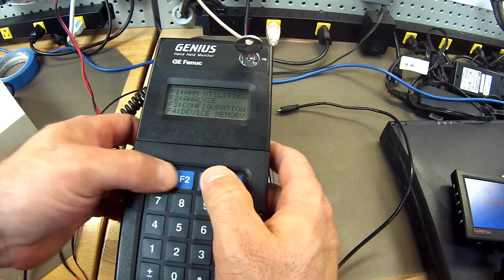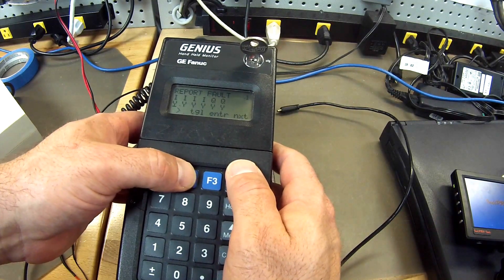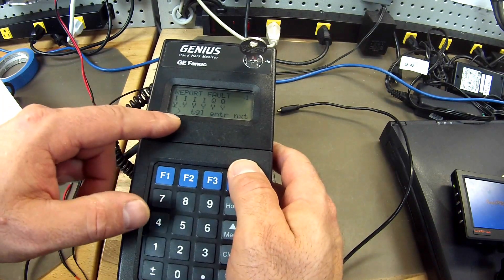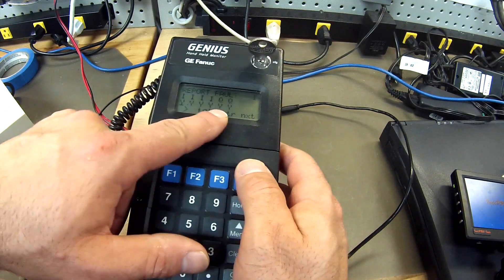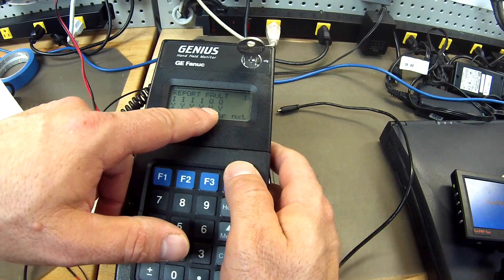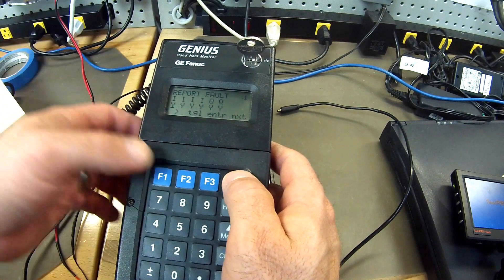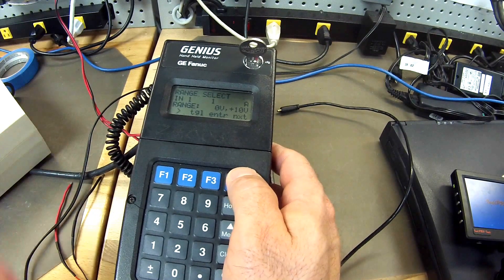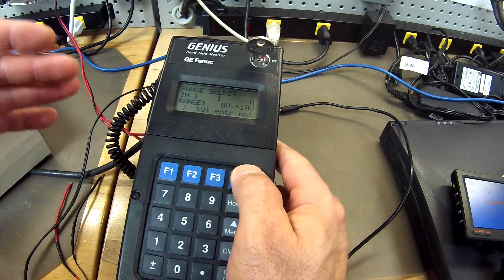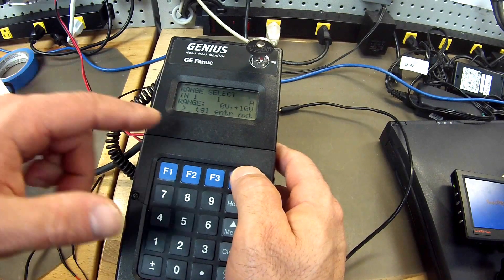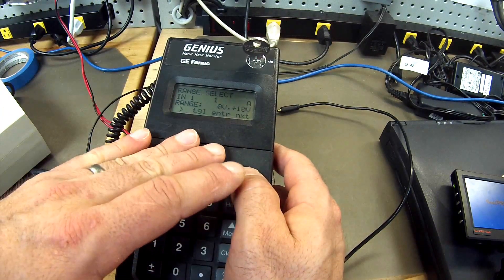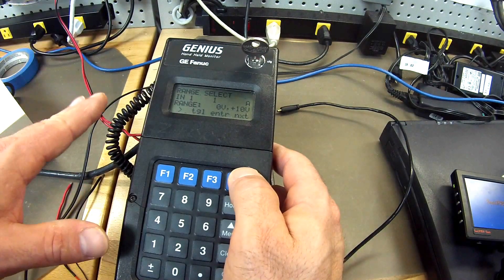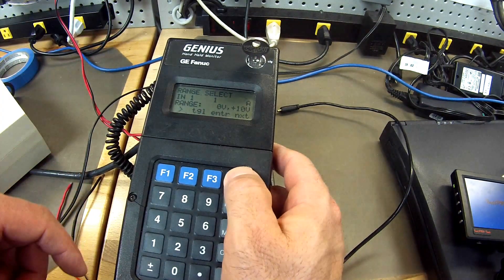And then I am going to go back to configuration, F2, configure block this time. This is set to the factory settings. Report fault input input input input output output. Yes, I do want to be able to report faults if there is an issue. And then here is something important. You want to set the range in which it is reading or giving power. Mine is set currently for zero to ten volts. So I am going to do a voltage test first and then a milliamp test next.